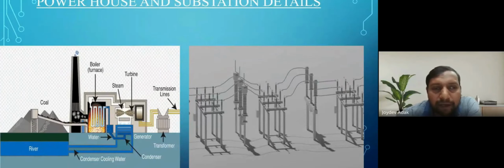One thing to keep in mind: for any generating station, between the generator and transformer there are normally no switching devices in on-load condition. For a 210 megawatt generator we use a voltage level of 15.75 kV, for 250 megawatt we use 16.5 kV, and for 500 megawatt we use 21 kV at the generator end. Then we step up that voltage to the transmission level through the generator transformer.